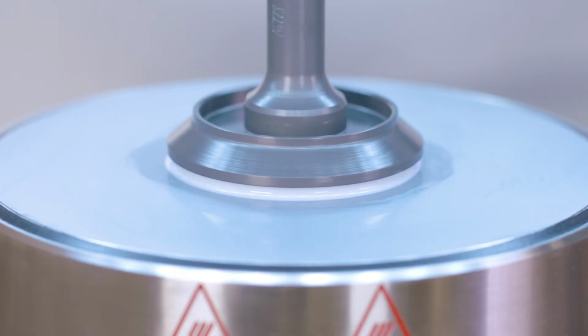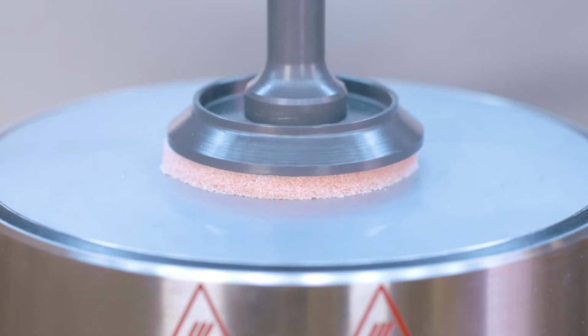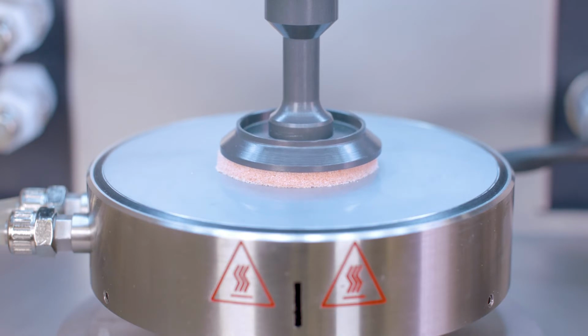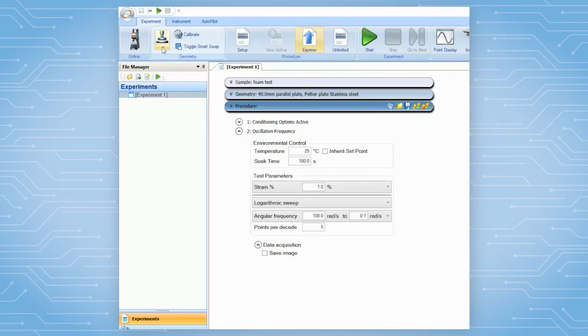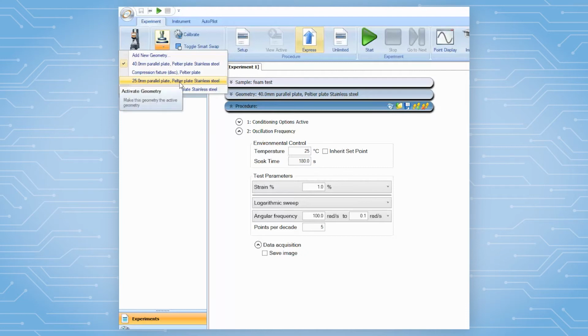Since this same parallel plate geometry can do both shear and compression measurement, it is important that the operator select the correct geometry name for the correct type of test. For shear testing, the operator should select parallel plate geometry. Then the instrument will move under shear deformation mode. For compression testing, the operator should select compression geometry, so the instrument will move in axial compressive mode.